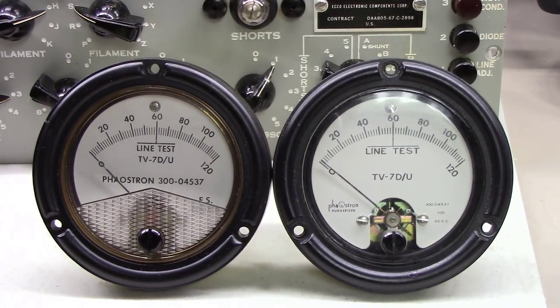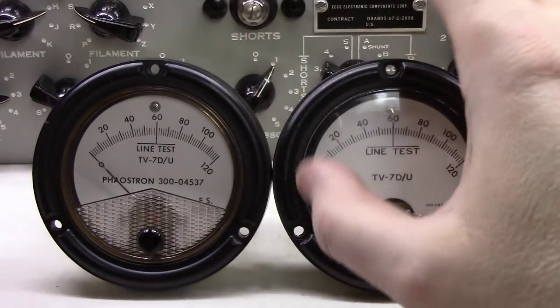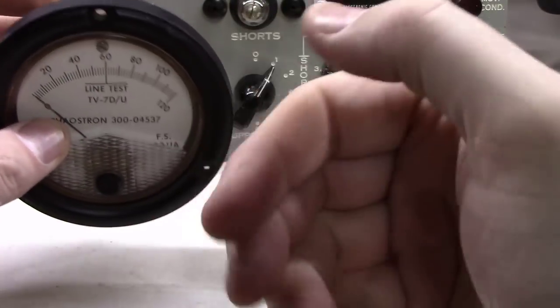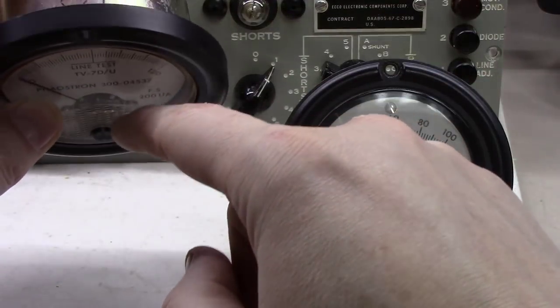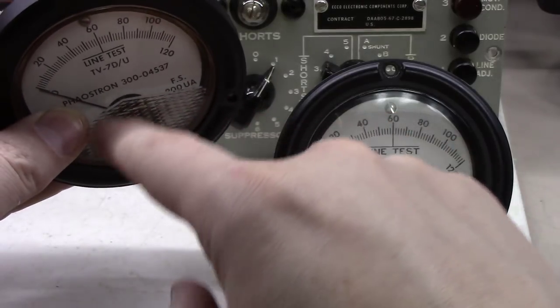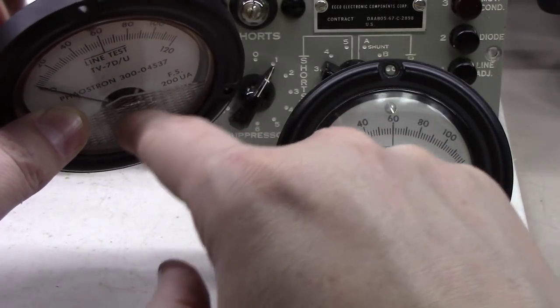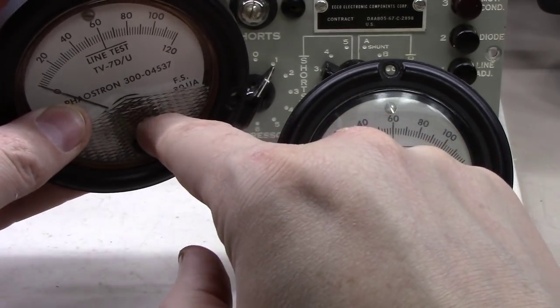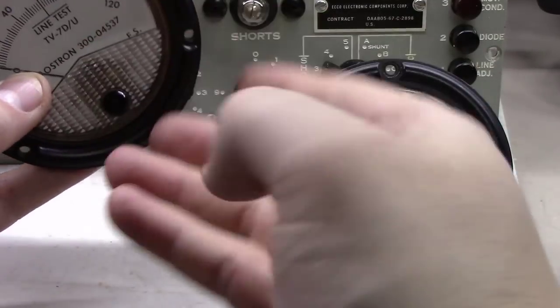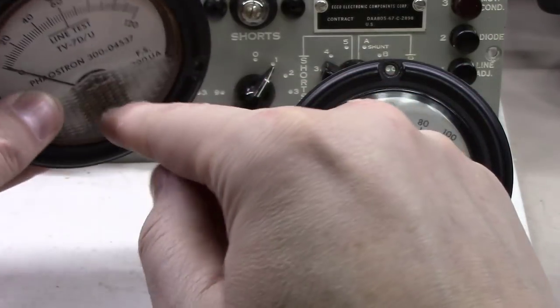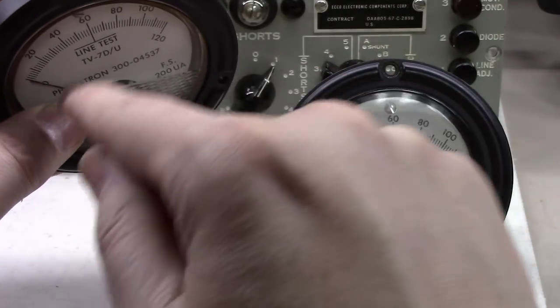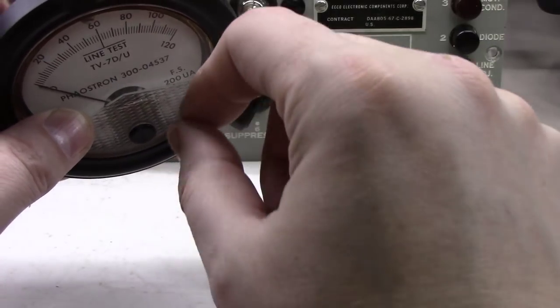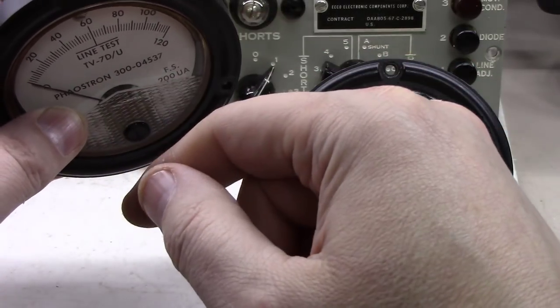One thing I would say about these sticky pivots, I have before, and I've read stories and talked to others where you can take the cover off and remove this acrylic housing, and you get down inside here and you want to blow out with some canned air or something very gently, just to make sure there's no dust or debris that has gotten inside of the magnet in there, because what you've got is a coil attached to the needle, and down in there is a magnetic frame that it's in, and if you get a piece of debris in there, it could cause the sticky meter issue.